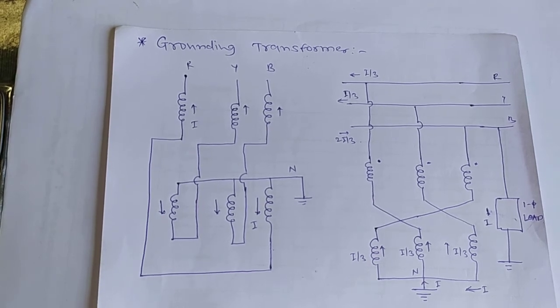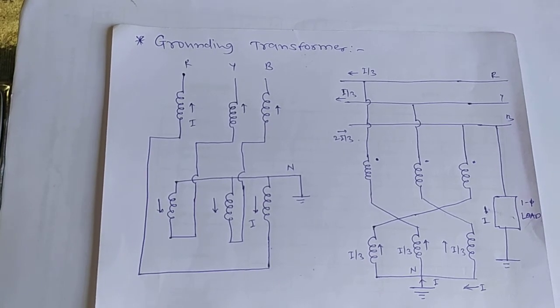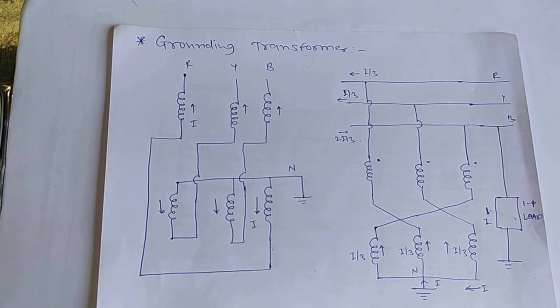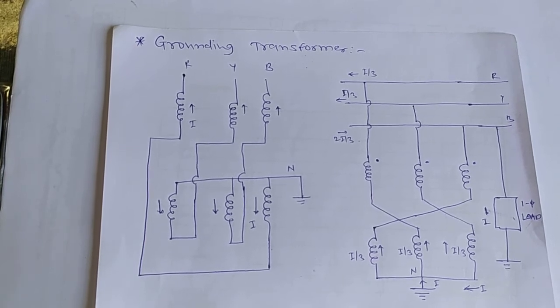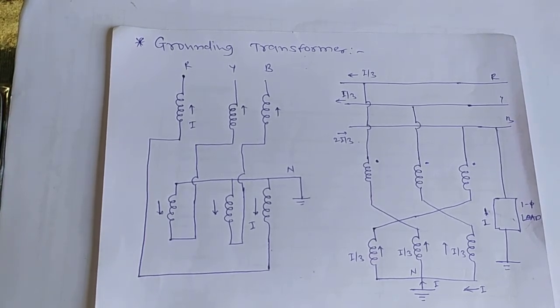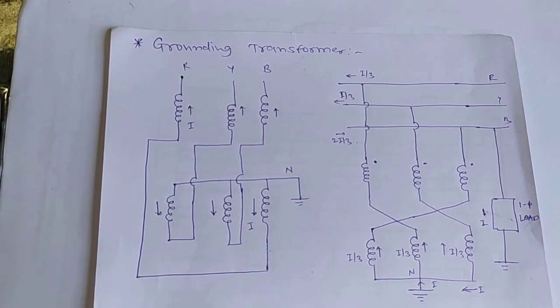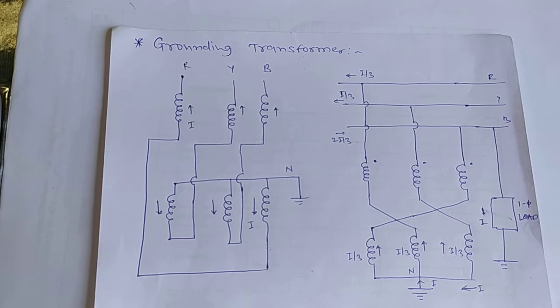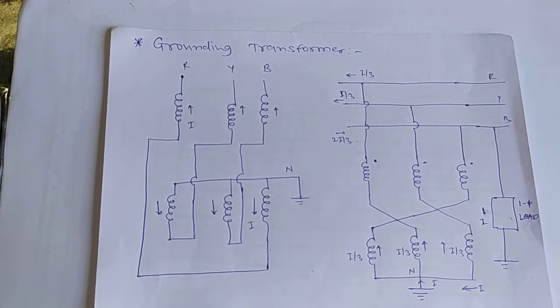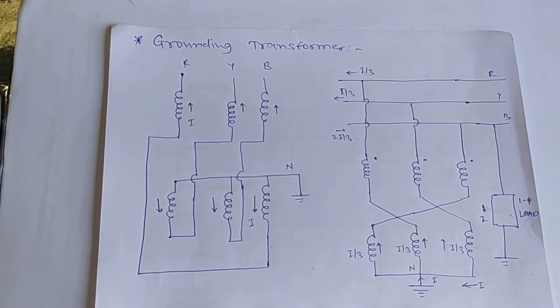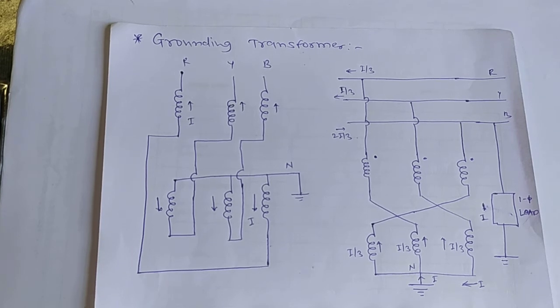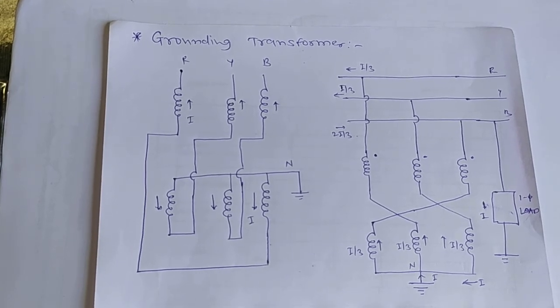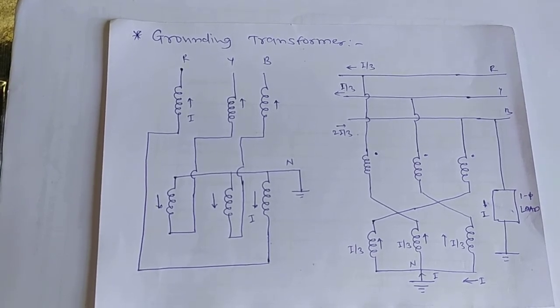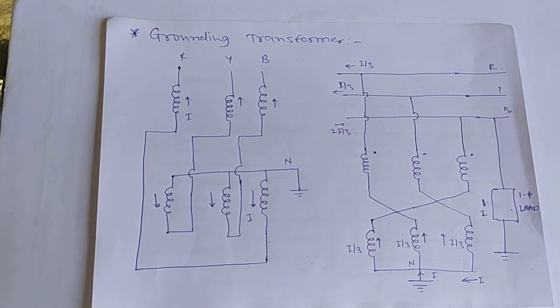Each limb of the transformer has 2 identical windings wound differentially, so the currents in the 2 windings on each limb are opposite to each other. Under normal operating conditions, the total flux in each limb is negligibly small. Therefore, the transformer draws a very small magnetizing current.